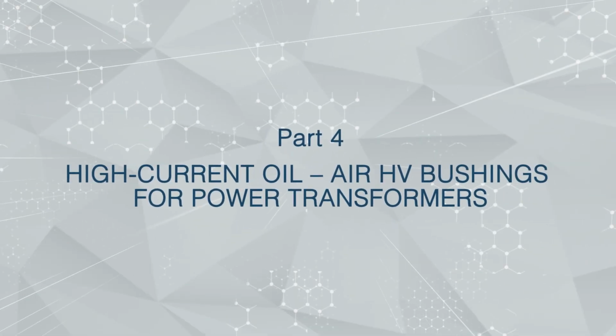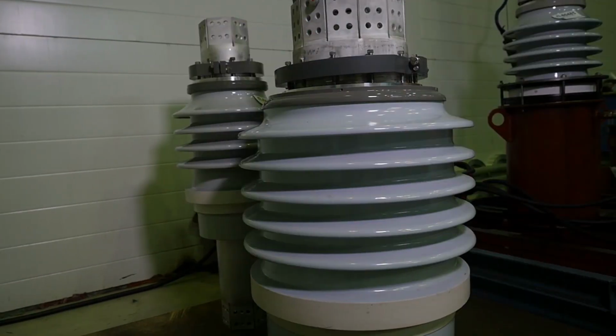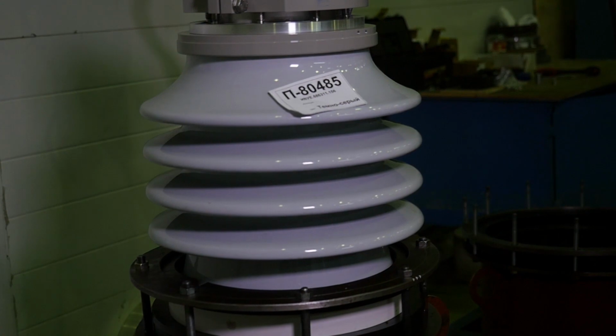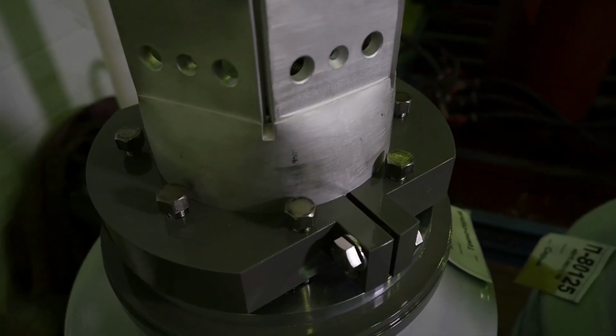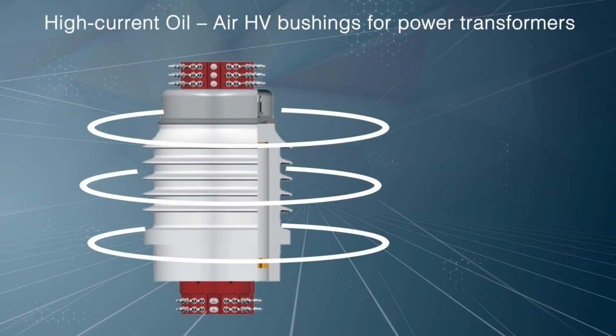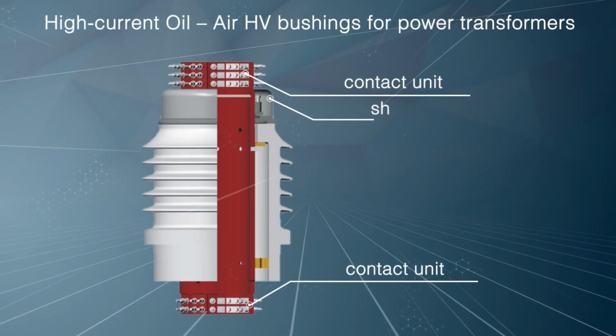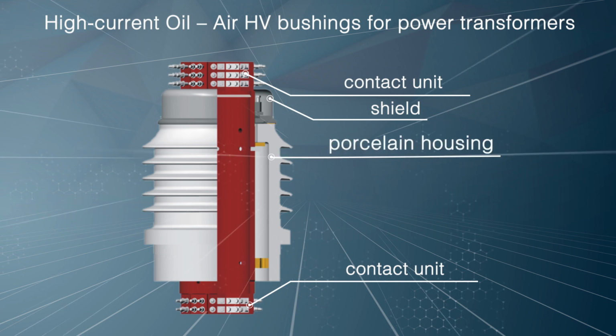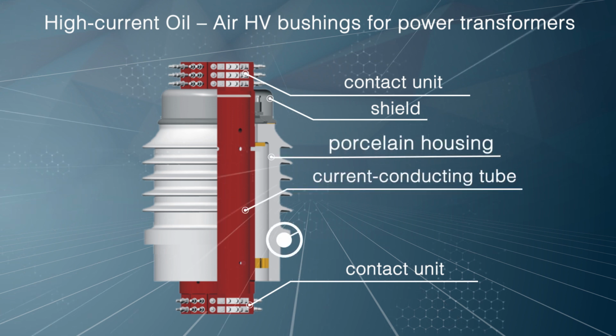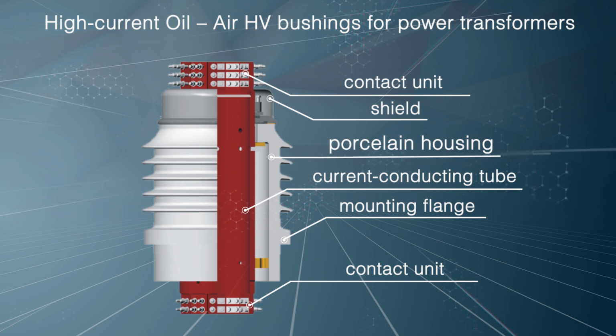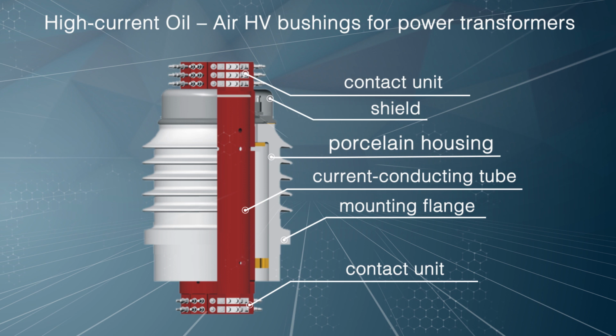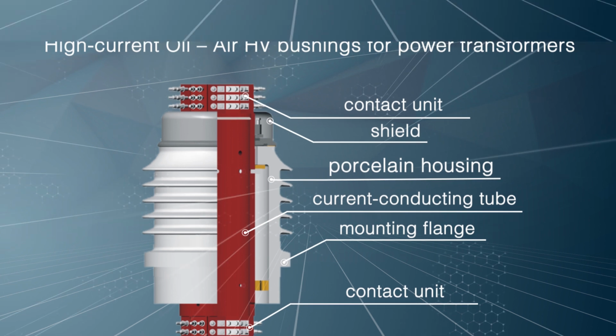High current oil-to-air high-voltage bushings for power transformers. These bushings are intended for connection and transmission of electric power produced by the generator unit of a power plant to the low-voltage winding of a power transformer. Design highlights of the detachable bushing. No internal insulation. Transformer oil fills the internal space of the bushing. Test tap is absent. Large surface of contact areas.